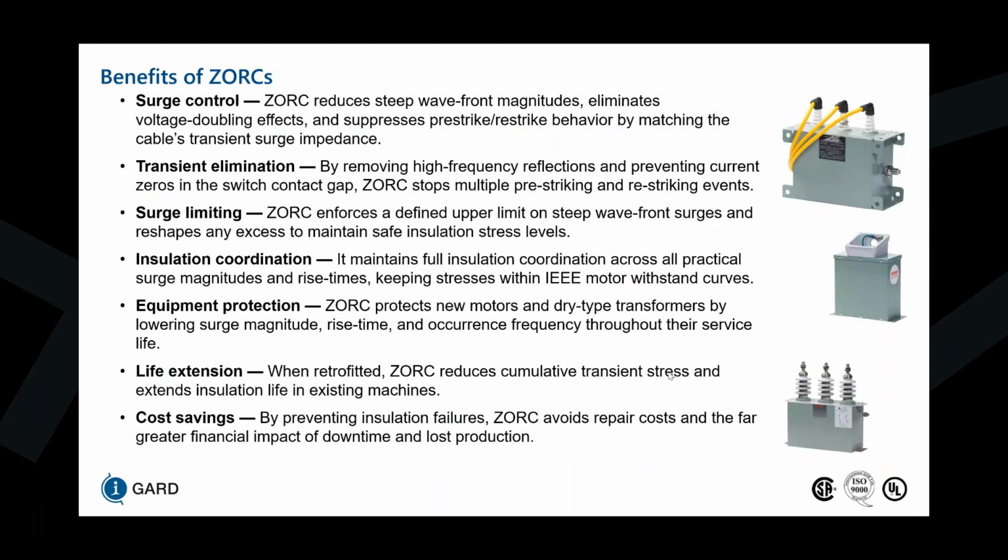So when you retrofit a ZORC, you're reducing the cumulative transient stresses on your system and you extend insulation life in existing machines. And that's where the cost savings come in. So you're preventing insulation failures on critical equipment. So ZORC avoids repair costs and the far greater financial impact of downtime and lost production for critical equipment, such as your motors, transformers, generators.